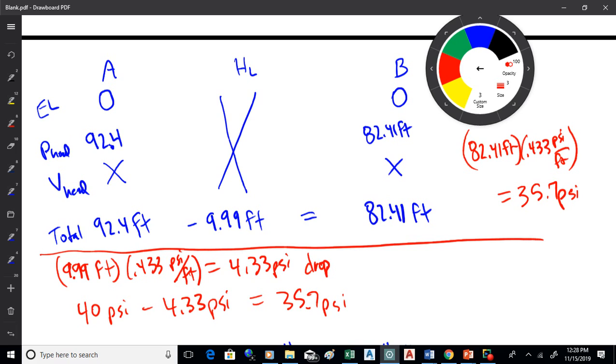And that's the only one we'll do using Darcy-Weisbach. I just wanted to get one in there just to get you a little bit of practice with that. As I've said, if you're doing stuff by hand, the normal way to do this stuff by hand is to do it with the charts and the Hazen-Williams stuff. Darcy-Weisbach is more accurate, but it's also obviously a lot more work to do, and that work may not be worth it given what you might be trying to accomplish.